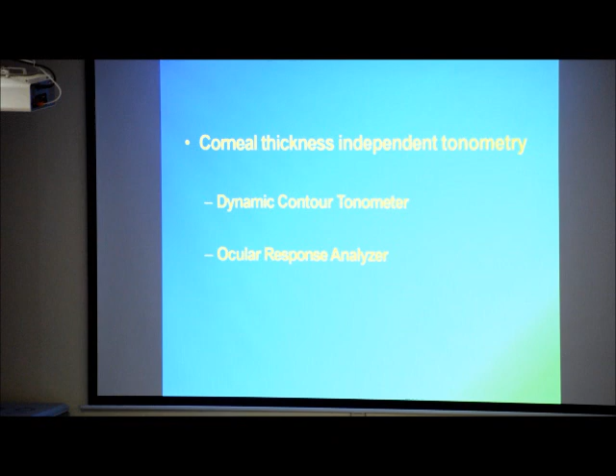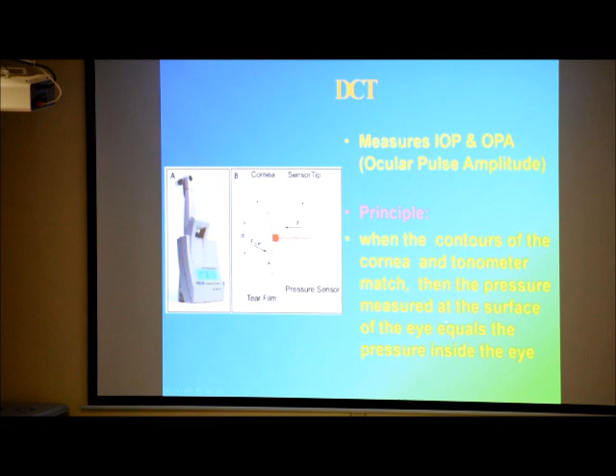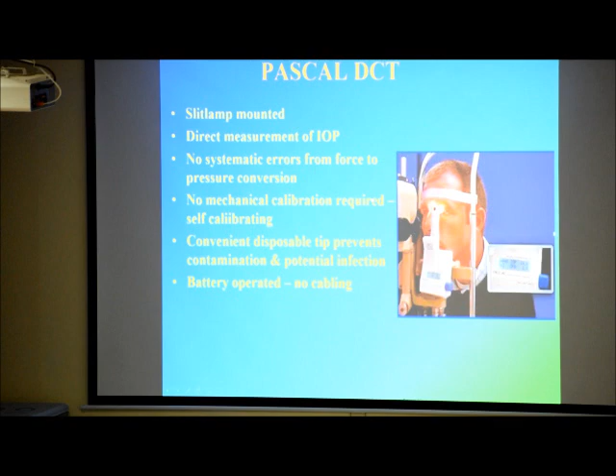The corneal thickness independent tonometers are the dynamic contour tonometer and the ocular response analyzer. The DCT measures intraocular pressure and ocular pulse amplitude. The principle is that when the contour of the cornea and the tonometer match, the pressure measured at the surface of the eye equals the pressure inside the eyeball. It is slit lamp mounted and gives a direct measure of the intraocular pressure, with no systematic error from force to pressure conversion. No mechanical calibration is required as it is self-calibrating, a convenient disposable tip prevents contamination and potential infection, and it is also battery operated.